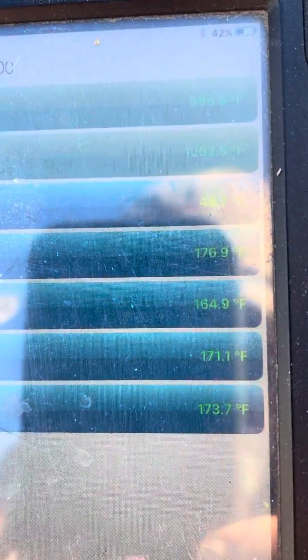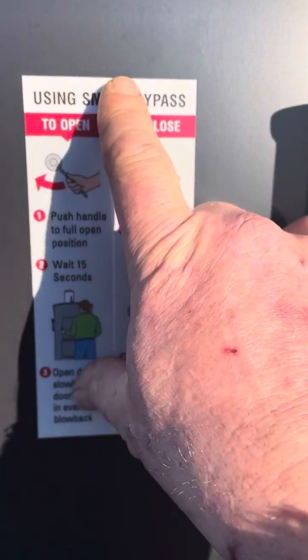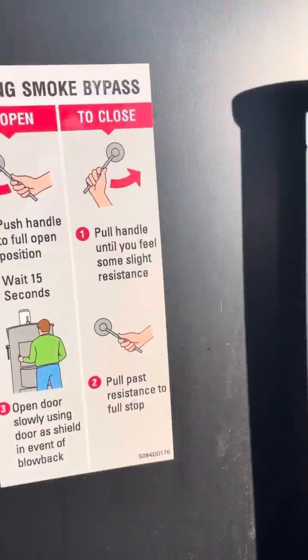If you're pulling a lot of flame through, that's going to top out well over 500. Still going up — I'm going to shut my bypass down now. I've not yet cooked the motor and I don't plan on starting. But even with the door shut it's still going up — 600 degrees.